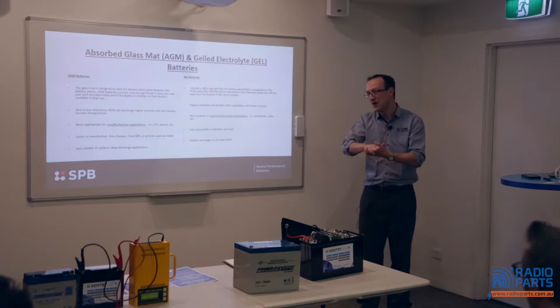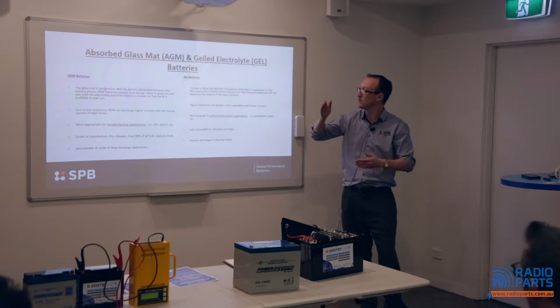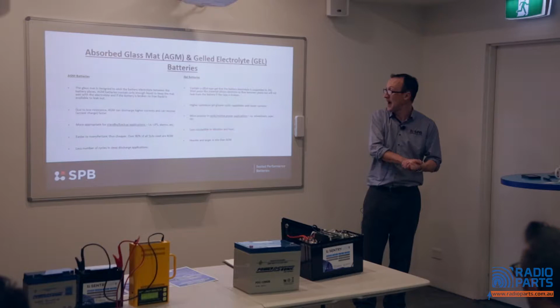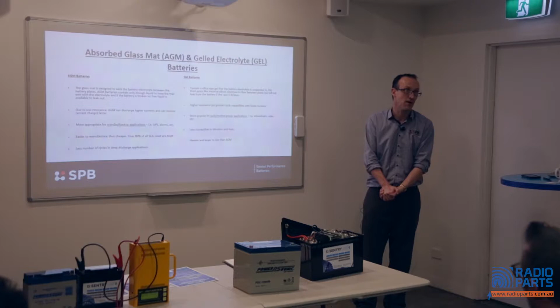However, with different purities of lead and strengths of acid, AGM batteries in cyclic applications are very popular, because they're cheaper. Over 80% of batteries on the planet are AGM batteries - it's cheaper to manufacture, volume is massive, and unit price is low. That's why you'll see cyclic AGM batteries in most caravans. Once upon a time, gel batteries were the in thing for caravans because of their better cyclic capabilities, but when people weighed up a marginally better performance of around 20% against paying 25-30% more for the batteries, gel batteries became more popular with industrial or high-end applications where the cyclic benefit is really needed, while AGM batteries remain dominant in cyclic use for the caravan industry.